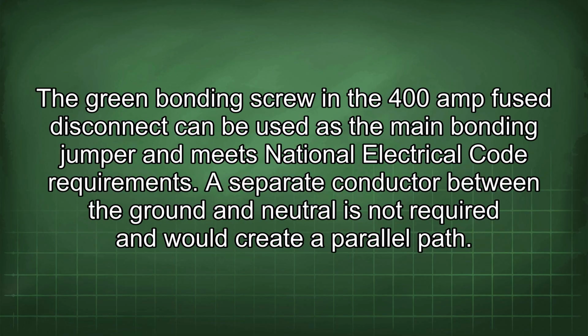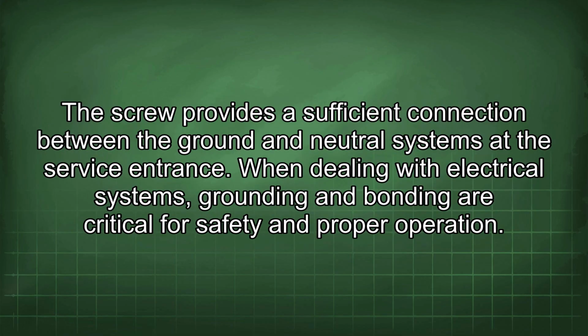The green bonding screw in the 400 amp fused disconnect can be used as the main bonding jumper and meets National Electrical Code requirements. A separate conductor between the ground and neutral is not required and would create a parallel path. This screw provides a sufficient connection between the ground and neutral systems at the service entrance.